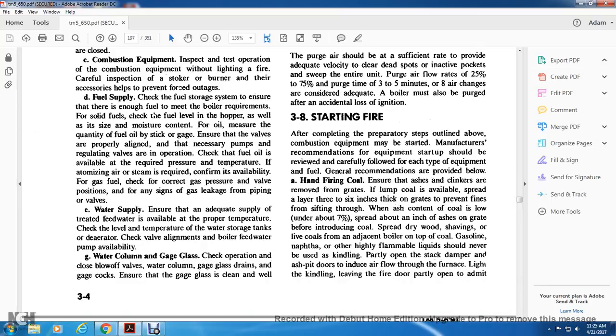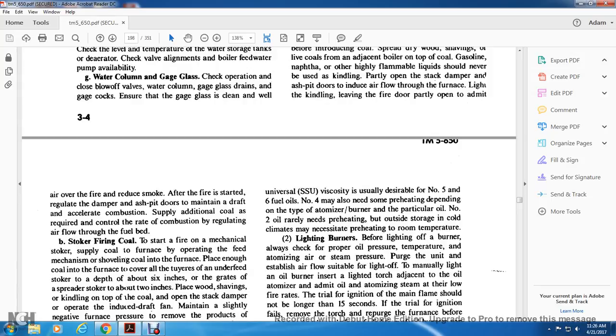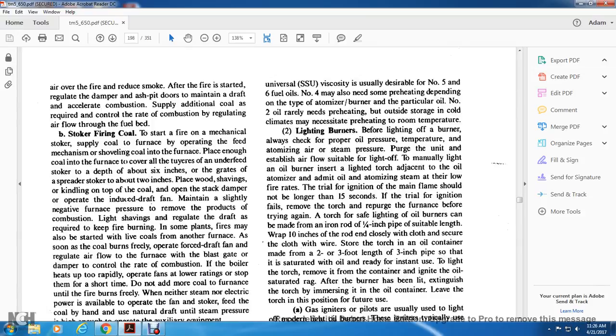3-8 Starting fire. After completing the preparatory steps outlined, the combustion equipment may be started per manufacturer recommendations. General recommendations provided below for hand firing coal: ensure ashes and clinkers are removed from the grates. Spread coal in 3 to 6 inches thick over the grates. Spread dry wood shavings with kindled coals from an adjacent boiler on top of the coal. Gasoline, naphtha, and highly flammable liquids should never be used for kindling. Open the stack damper and ash pits to introduce air flow. After the fire has started, regulate the damper and ash pit doors to maintain draft.